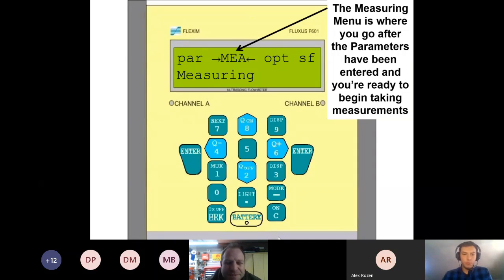So the sound speed's a great diagnostic for a few things. A, making sure you have the correct parameters and the correct pipe. B, making sure you're measuring the correct media. I've done stuff on chilled water before where everybody swore up and down to me that it was just straight water, but I was getting a diagnostic that was in the 1600s, which is indicative of glycol. Then someone walked by and was like, oh no, we use 30% glycol. And then the past 2 hours of troubleshooting were useless because I was right all along. It was just an error on communicating to me what media it is. So it's a very powerful use of a diagnostic.